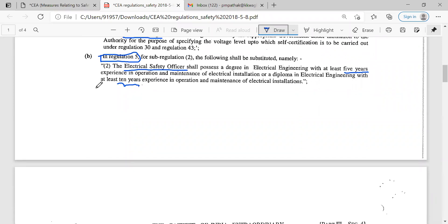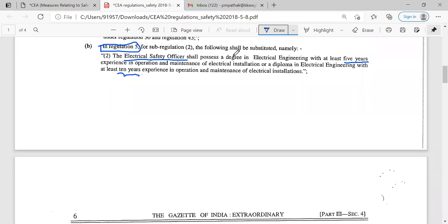There is another change in regulation number 5, that is electrical safety officers. With reference to this 2018 rule, the electrical safety officer is required to have a basic education qualification of electrical engineering graduate but with minimum 5 years experience. Now, in the 2010 rule it was minimum 10 years experience — now it is modified to 5 years. For the diploma electrical engineer that is 10 years, whereas before 2018 that was 15 years, so that is modified to 10 years.